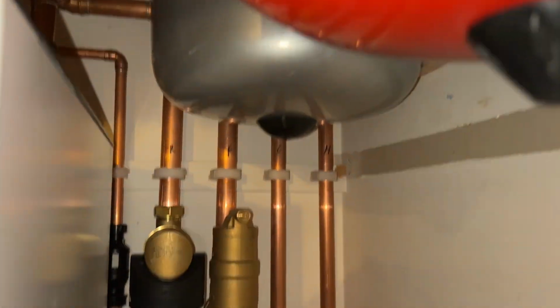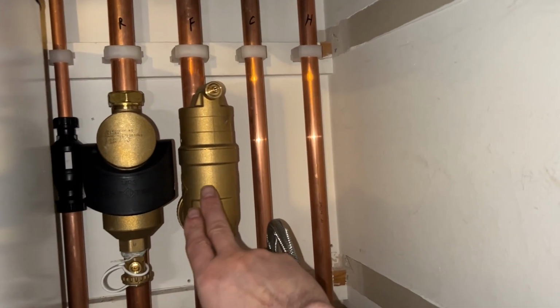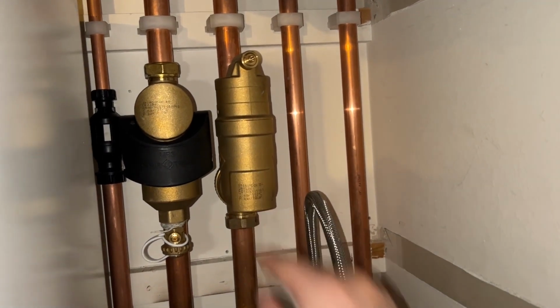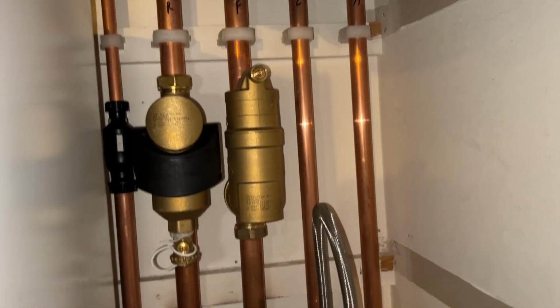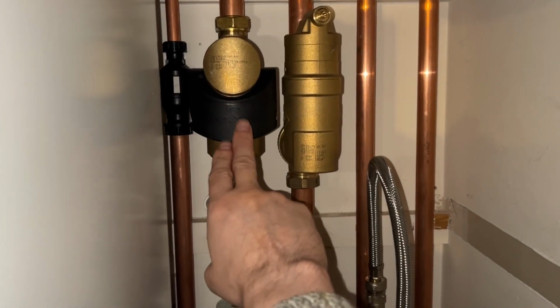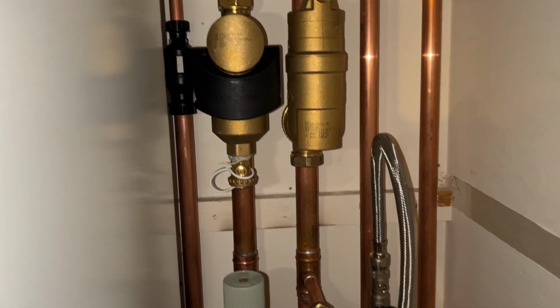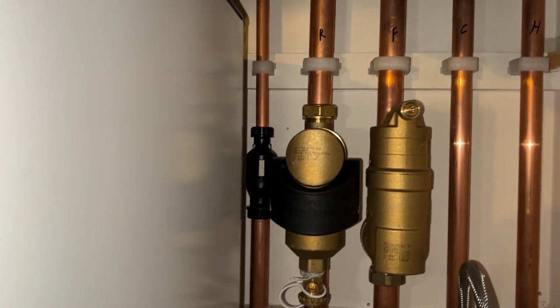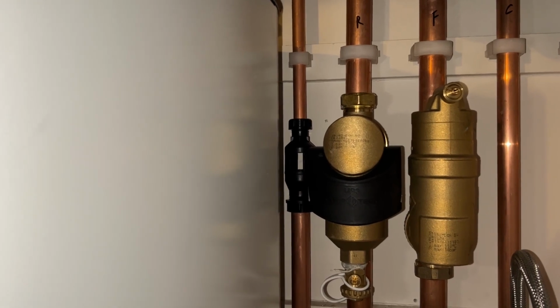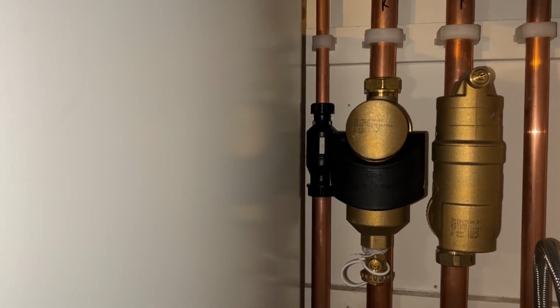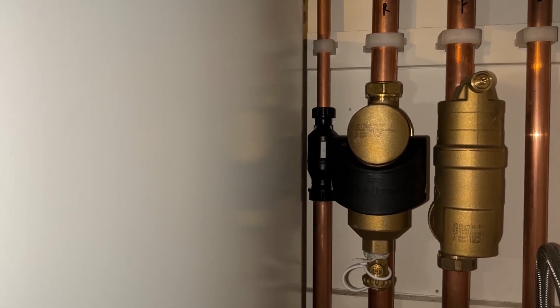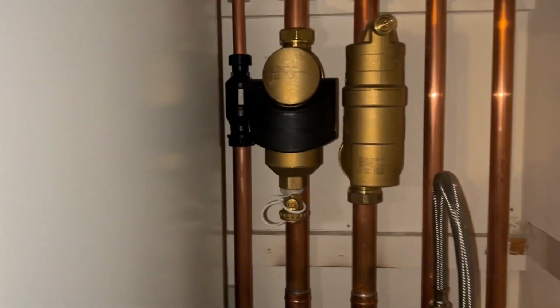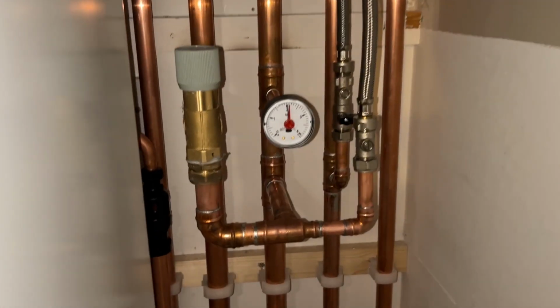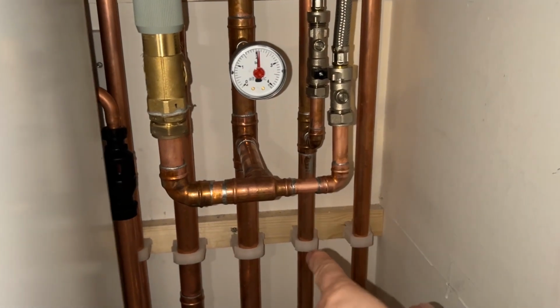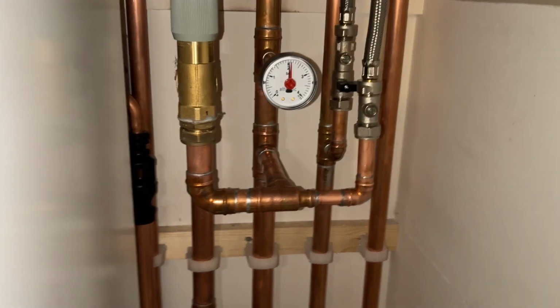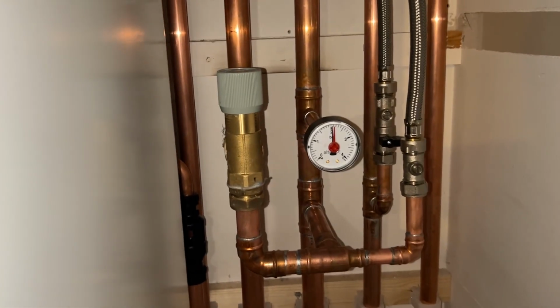One thing about the flow and return is the flow side. That is a deaerator, so that removes all the micro bubbles. And then on the return side, we've got this. This is a magnetic filter, and that will collect any iron oxide particles. We've got these things called tun dishes, and they are used as a quick visual reference to see whether there's any overflow from the hot water tank because of expansion tank issues. We've got a pressure gauge, and then we've got a filling loop from the cold water supply. And we have got this bypass valve as well.